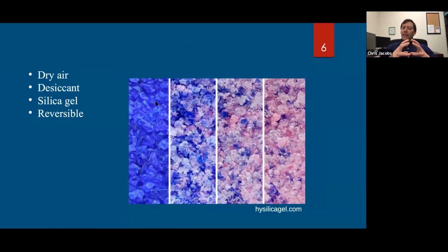And I mentioned that in order for air to have a specific gravity of 1, it must be dry, meaning it must have no moisture in it, because moisture will change the density of the air. In order for us to get an accurate specific gravity, our reference material has to be at the standards for air, which is dry, 20 degrees Celsius, and 1 atmosphere. So we have to remove any moisture that might be in the air, from the air. Otherwise, we will get an incorrect reading.